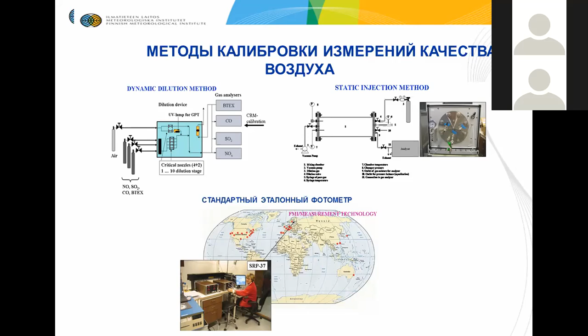Okay, here is some more methods for this calibration. So there is this gas phase titration method, one of the methods, where partly you have the gravimetry system for the gas standard needed for that. Of course, very important is the gas flow calibration method that is also traceable to the SI units, and of course you understand that now we are talking about very low gas flows that have to provide a good accuracy.